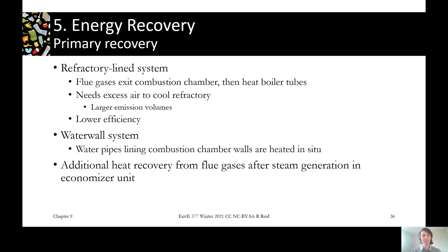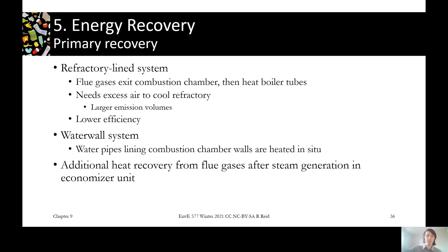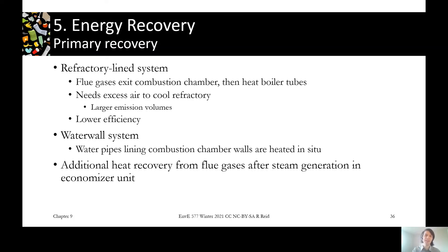The next step is energy recovery. There are two modes in mass burn systems. One is the refractory-lined system, where refractory brick — a material highly resistant to heat — lines the reactor to keep heat in, and the hot flue gases are piped to a separate boiler where heat exchange takes place. The other approach is the water wall system, where heat exchange happens right inside the reactor itself. The boiler water is piped through the walls so it heats up directly in the reactor.